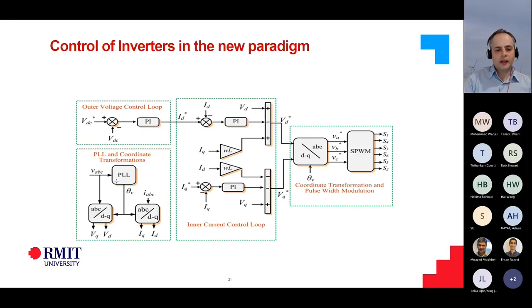But all of that relies on the fact that the voltage at the point of connection is of very good quality. Now, that's not going to be the case in future, because if we are losing lots of our voltage sources like our synchronous generators, we won't be having a perfect voltage source in the terminals, particularly if the inverters or the renewable energy sources are far from the strong points in the grid. So if we are dealing with weak connection points in the grid, these problems are going to be more significant in the future.